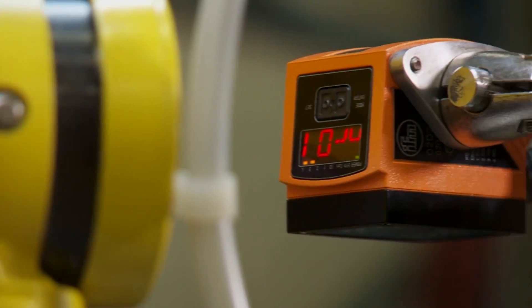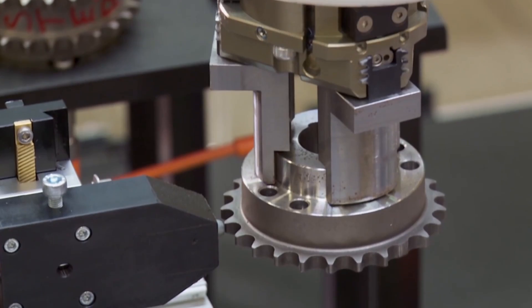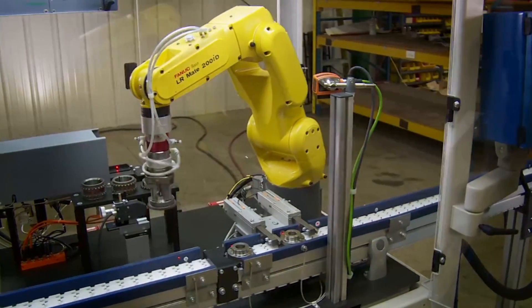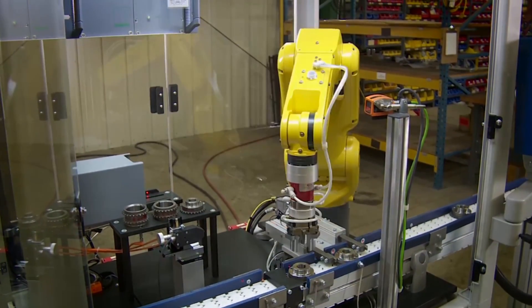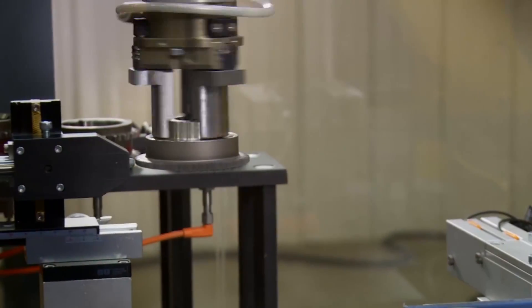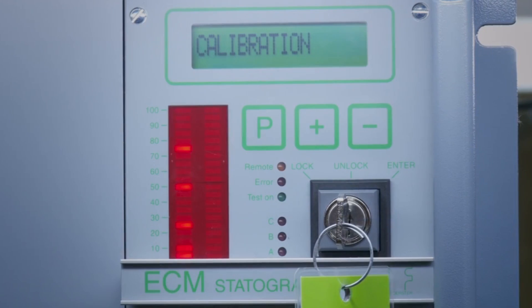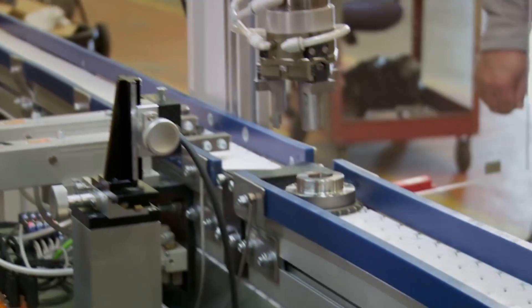This test station uses a complete multi-axis FANUC LR-Mate 200ID robot to handle both component transferring and testing. The machinery and technology used is dependent on your particular application and product. The Foerster Statograph ECM and Magnetest D non-destructive testing technologies are used to check for cracks and heat treat results.